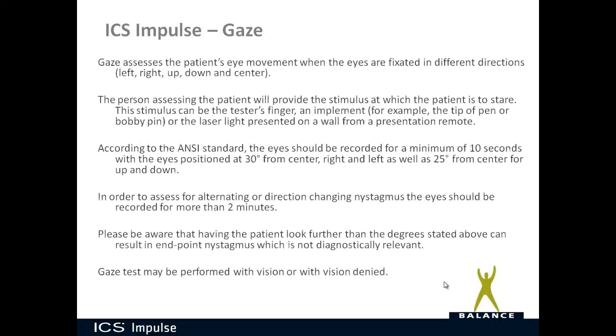Gaze assesses the patient's eye movement when the eyes are fixated in different directions, typically left, right, up, down, and center. The person assessing the patient will provide the stimulus at which the patient is to stare. According to the ANSI standards, the eyes should be recorded for a minimum of 10 seconds, with the eyes positioned at 30 degrees from center for left and right, and 25 degrees from center for up and down.